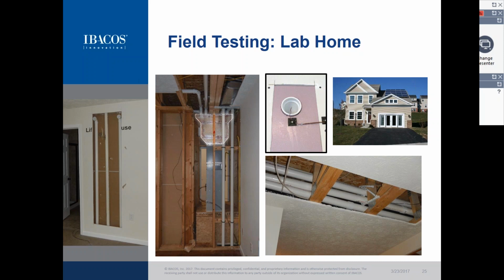With the way we believe the routing would work, you wouldn't route the ducts through a 2x4 structural wall horizontally; it would go vertically up through a wall. The ways we've installed the ductwork so far haven't had any structural deficiency issues. If you tried to route a 3-inch duct horizontally through a stud wall, you'd eliminate a lot of that structural member, which wouldn't be a good scenario. That's why we're looking at vertical runs through those stud walls, and horizontal runs through other stud bays or floor cavities, above or below a zone.